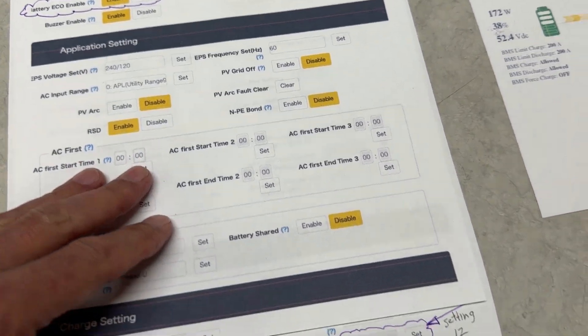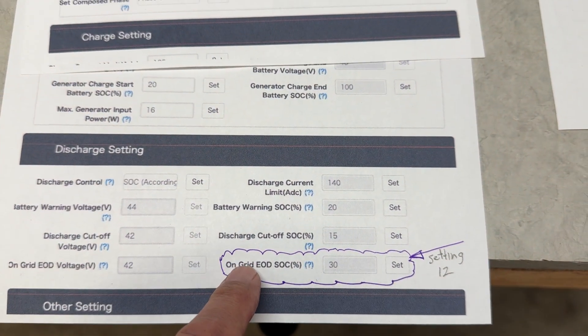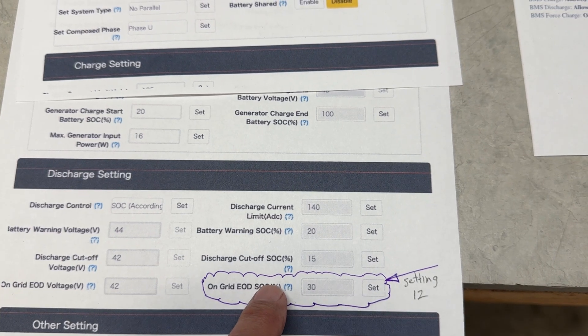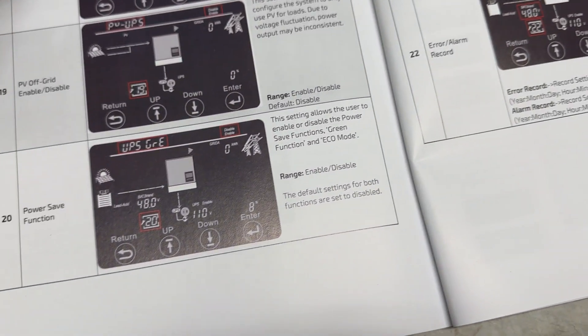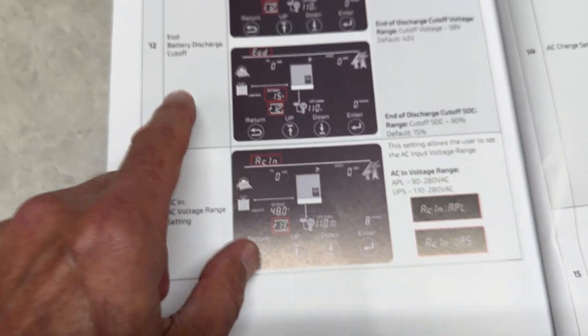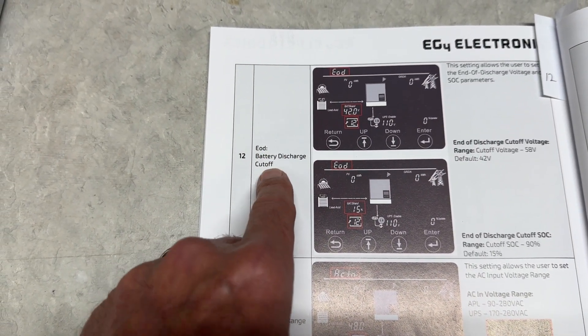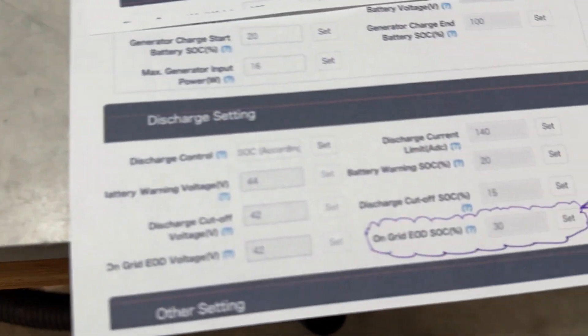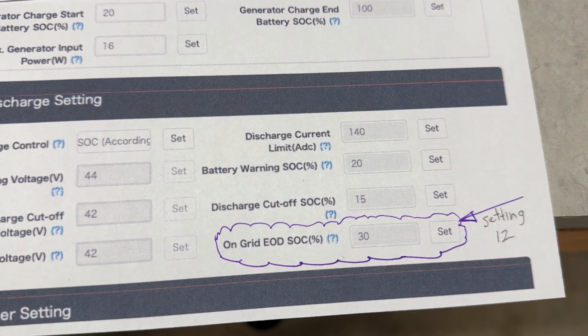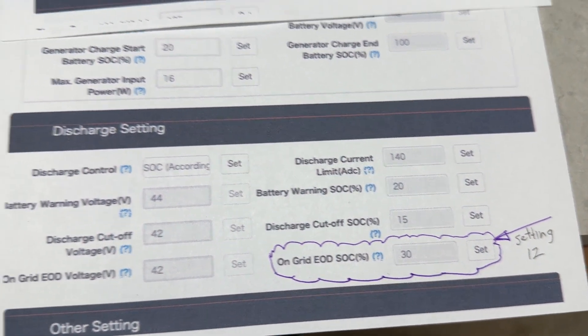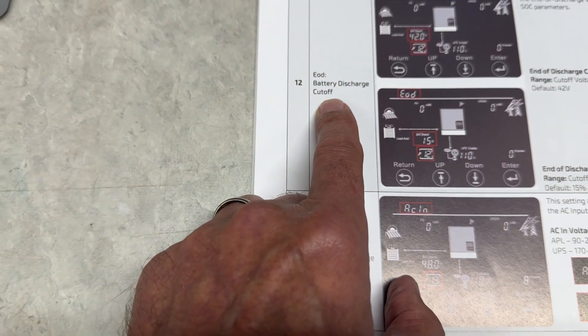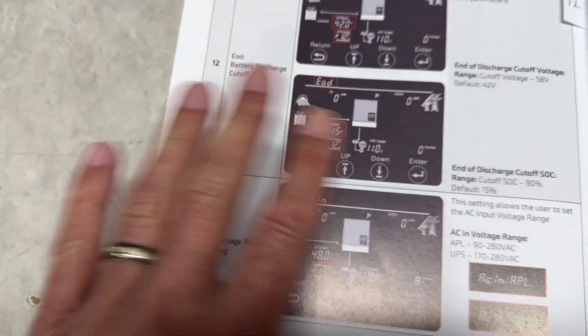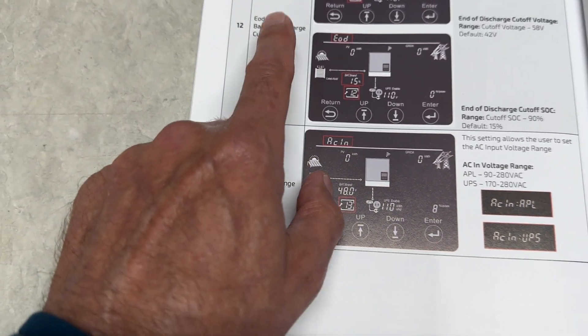The next setting is on grid end of discharge state of charge. I have it set to 30. That is setting 12 in the manual. If you look at this title of this setting, it's slightly different than what you see on the app. This is on grid end of discharge state of charge. This doesn't say on grid, it just says end of discharge battery discharge. It's just more stuff that's confusing.